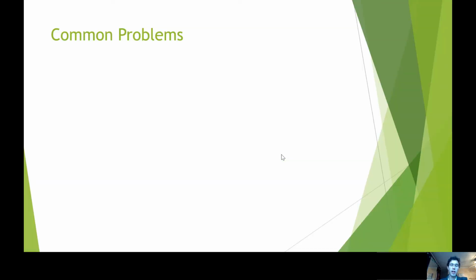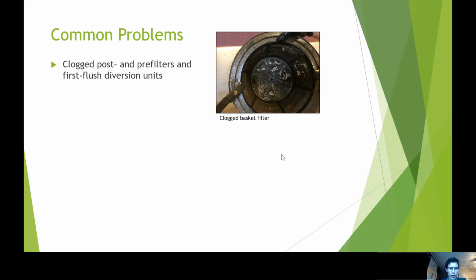So, conclusions. There are a number of problems I have seen and experienced up until this point, and am continuing to see and experience. The first of which is very common: pre- and post-filters being clogged, and the first flush diversion units being clogged as well. These are pieces of equipment that are great to have in a rainwater harvesting system, and can be considered nearly an essential component. However, if they're not cleaned, there's no benefit, and if anything, they can serve as a source of problems. So if they're not going to be maintained, it's better to not have them at all. The fact is, they're there in the design of some of these systems. They can be a great asset in preventing medium to large size debris from entering the tank.